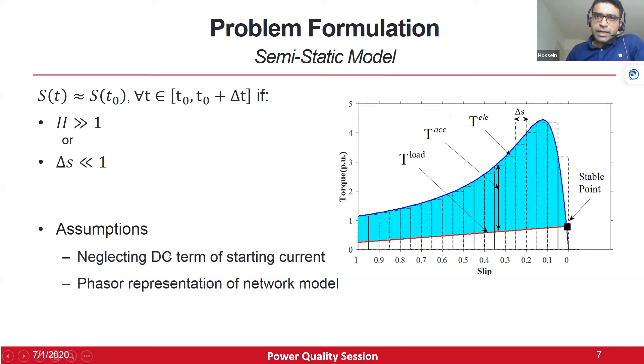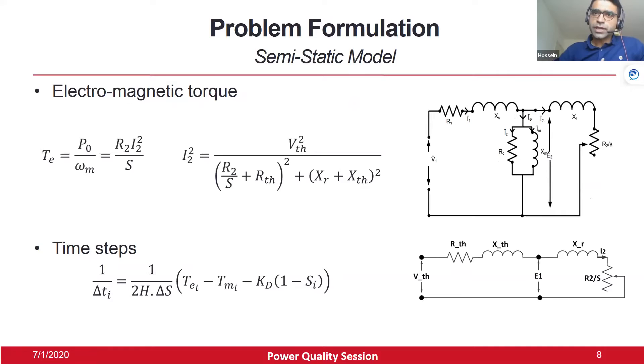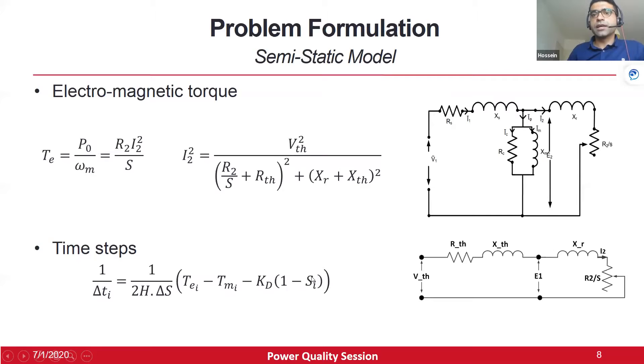Additional assumptions include neglecting DC terms of starting currents, which is fair for resistive distribution networks where the DC component disappears shortly after motor starting. The network is modeled in phasor mode. The electromagnetic torque is a nonlinear function of the slip value, so we fix the slip at each step as a parameter and derive the time duration of each step as a variable in terms of the slip value.